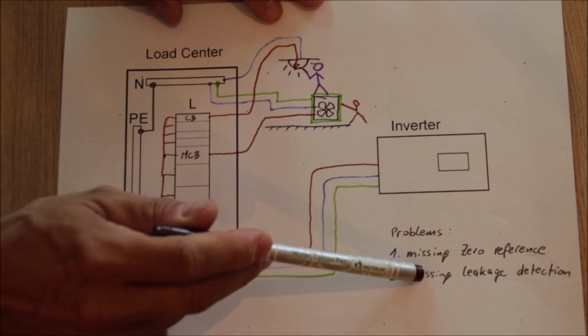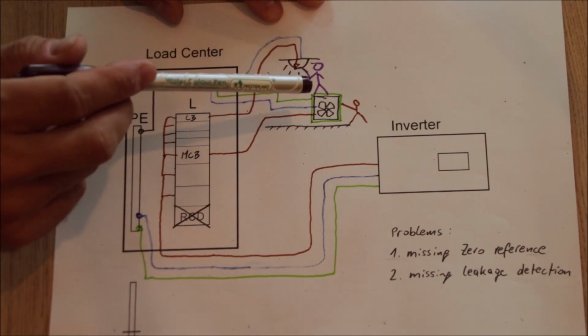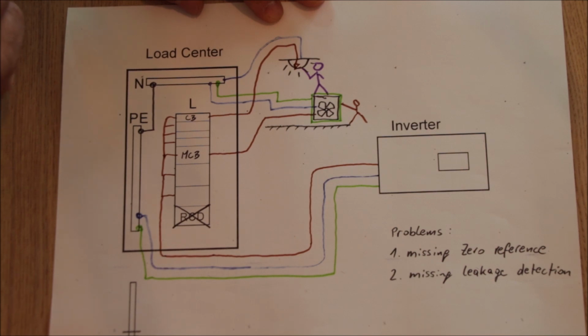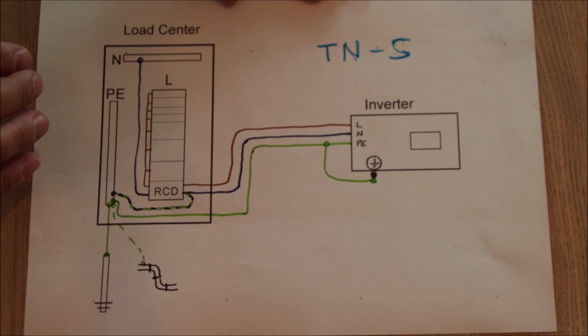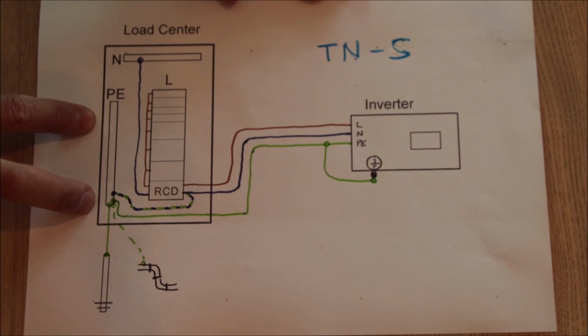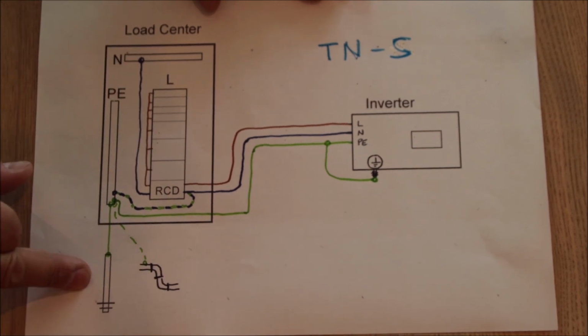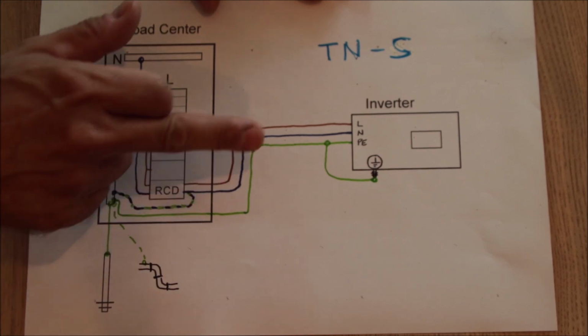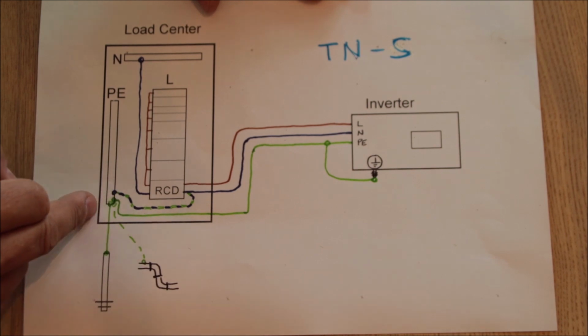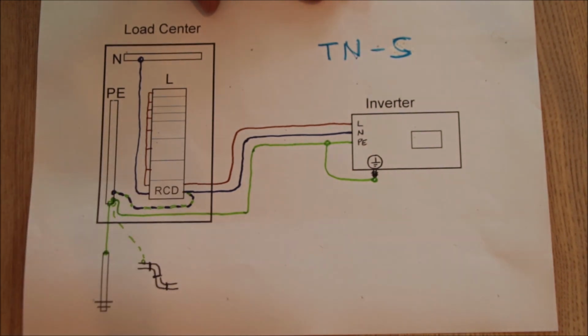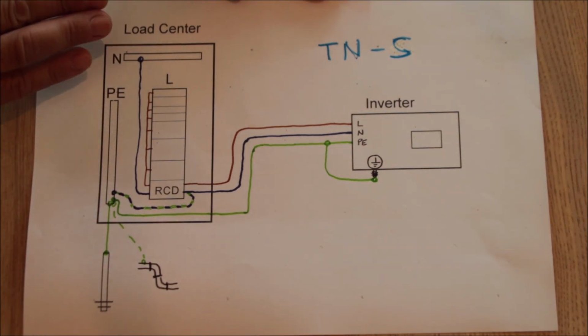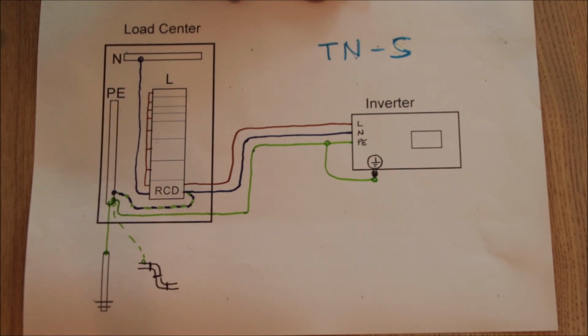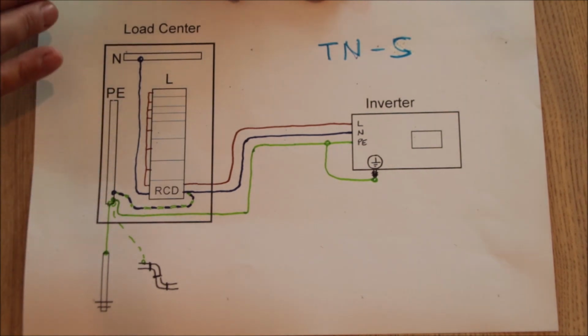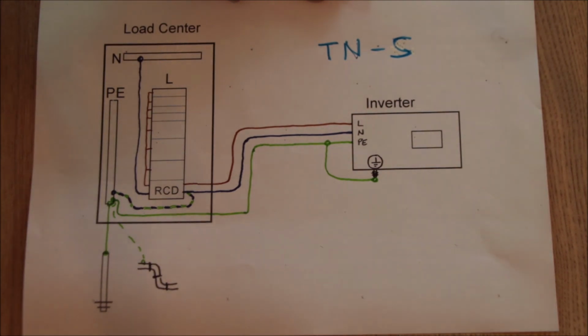Without an RCD we don't have leakage detection, and nothing in the world can stop you being electrocuted in this situation, other than maybe gravity if it pulls your hand away. So that's why it's absolutely important to follow the installation. Use an RCD, split up PE and working neutral, use a earthing rod, connect all other stuff with earthing which needs to be, and make your bonding wire from the PE bar to the input of the RCD neutral. This setup will cover any earthing fault, any leakage, and also most of the dead shorts by the RCD. And what is not covered by the RCD, it will be covered by the circuit breakers.